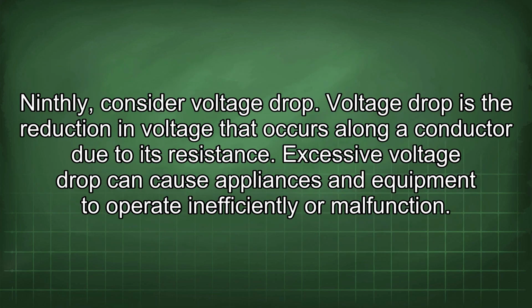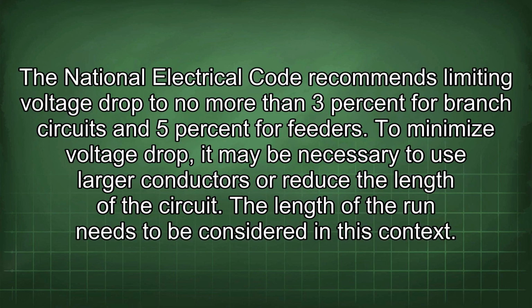Ninthly, consider voltage drop. Voltage drop is the reduction in voltage that occurs along a conductor due to its resistance. Excessive voltage drop can cause appliances and equipment to operate inefficiently or malfunction. The National Electrical Code recommends limiting voltage drop to no more than 3% for branch circuits and 5% for feeders. To minimize voltage drop, it may be necessary to use larger conductors or reduce the length of the circuit. The length of the run needs to be considered in this context.